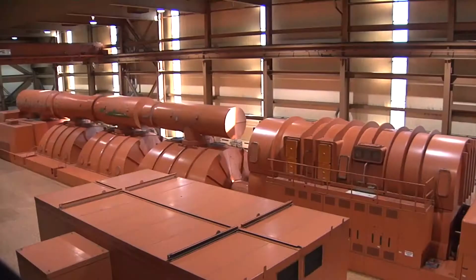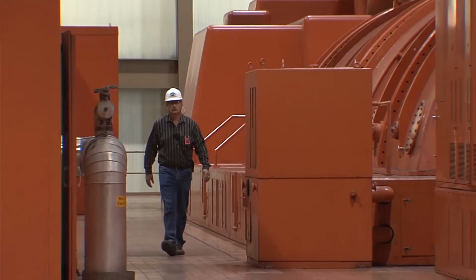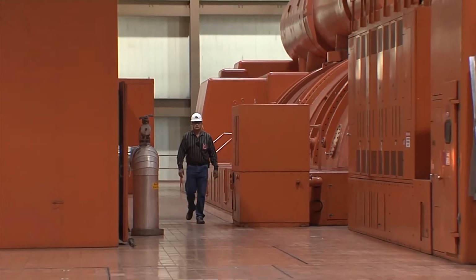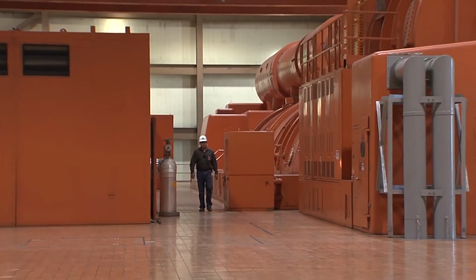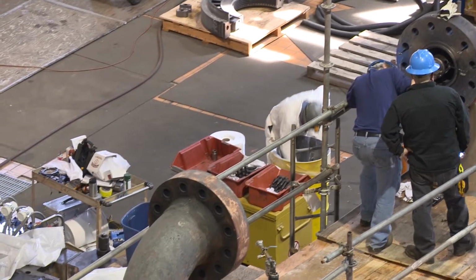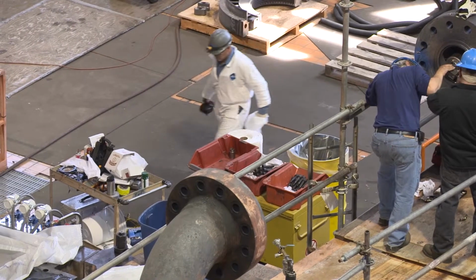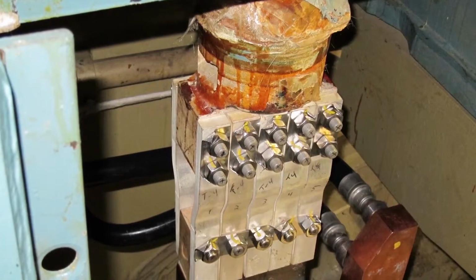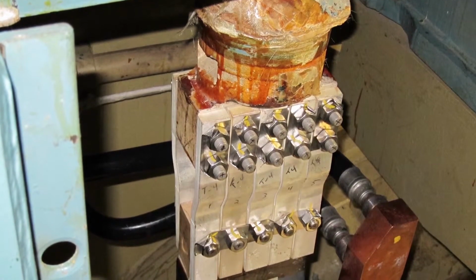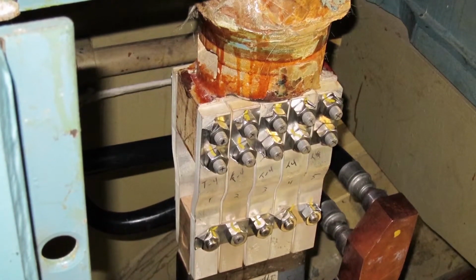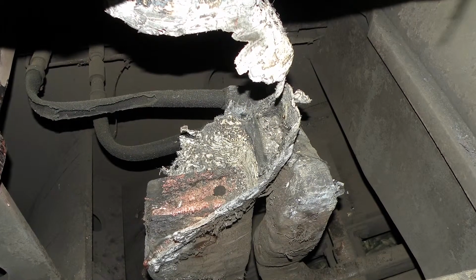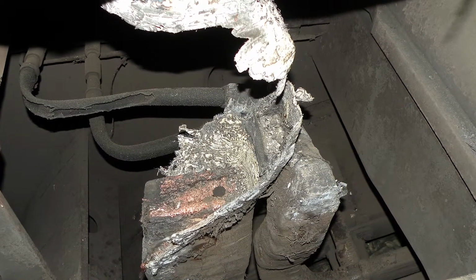In the first 9 months of 2011-2012, challenges continued with an unusual equipment failure that led to a 151-day unscheduled repair outage for Unit 1. On December 28, 2011, a connector in the Unit 1 generator catastrophically failed. The total cost to repair Unit 1 was approximately $17 million, and the performance impact of this single equipment failure was significant.